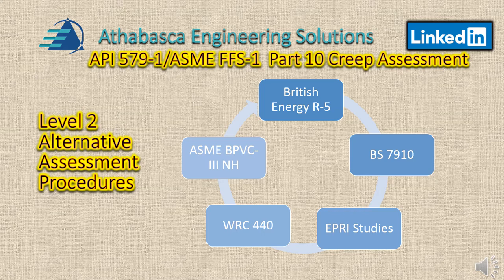EPRI has published studies related to CREEP assessment, though they are quite expensive to obtain. The WRC 440 has some really interesting data with lots of experience summarized there. And of course, ASME has the boiler pressure vessel code, Section III, Subsection NH, which is the nuclear code.